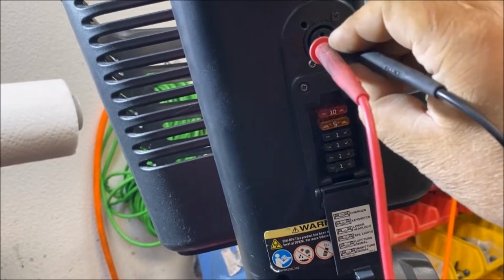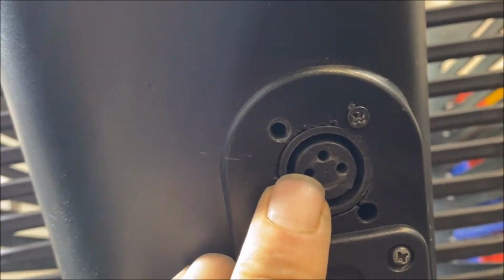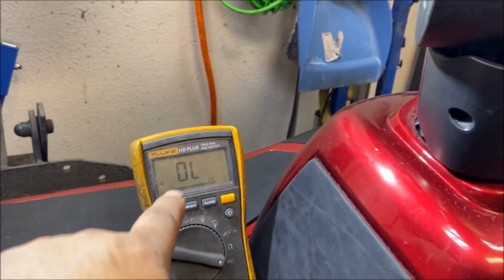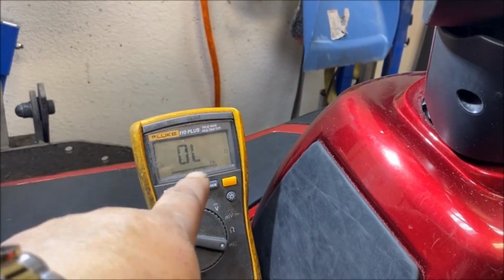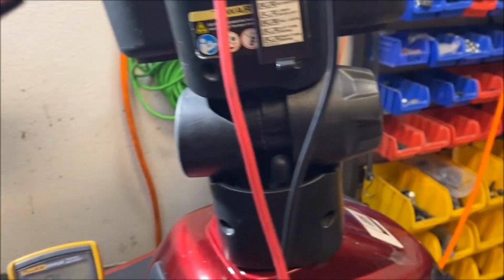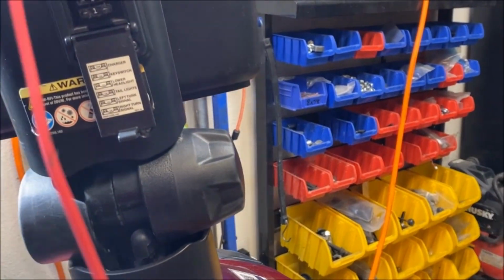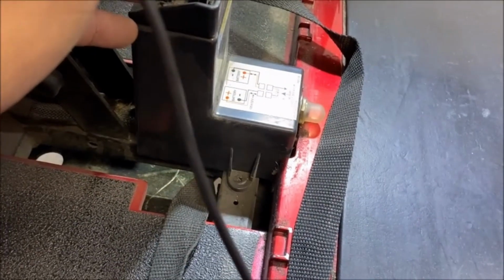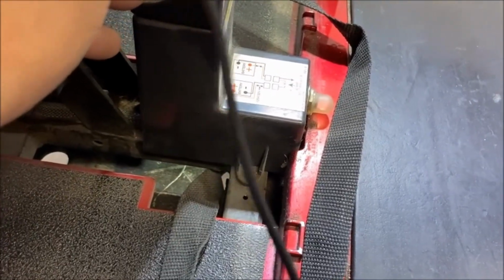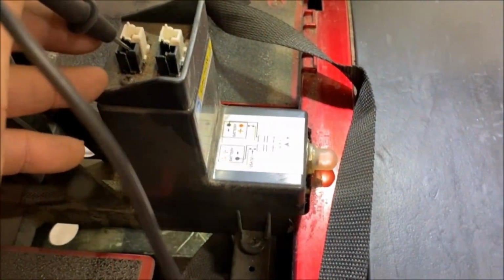That's how you would normally test if you have power at the charge port. You put the prong in either of the two holes, one left and right. It doesn't matter which way round, it'll just read negative or positive. Put one in either side, and then you should have a reading on your screen of 26 plus volts, and a beep on the tower.